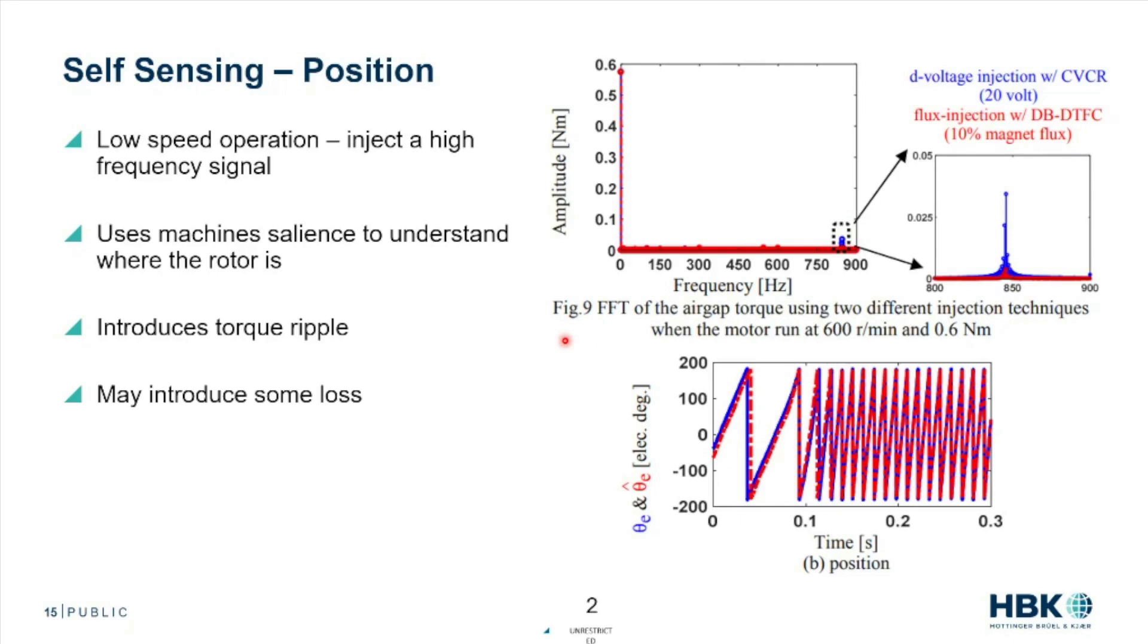And that gives us the ability to sense where the rotor is. This basically uses the machine saliency. We pulse the signal at the rotor, we read back what it's telling us. By injecting a high frequency or a harmonic injection, we can understand where that rotor is and gives us a lot of tools for controlling and predicting what the machine is going to do.